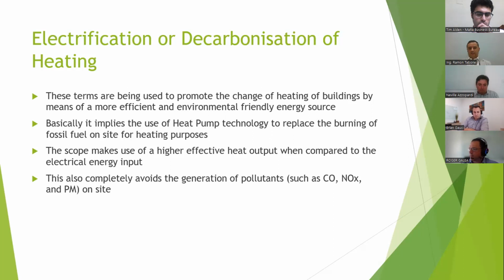For the non-technical, I'll explain this in brief. To dehumidify the air, you first cool the air excessively. What in HVAC we call, you go below the dew point. So you condense the water from the air, but then you cannot send the air into the wards and the rooms at that very low temperature because you'll get discomfort. So what we have to do is reheat it again to a comfortable temperature. And that's where the heat demand comes from in HVAC.